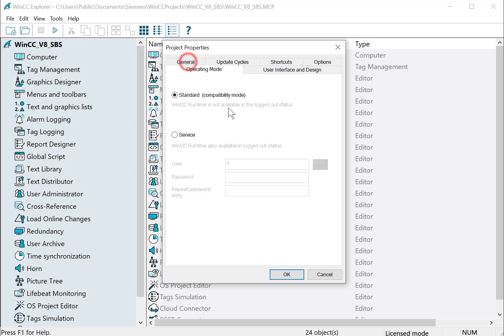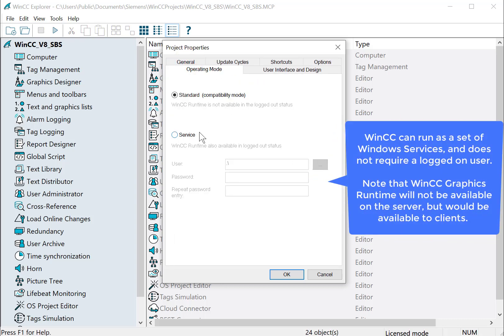And under Operating Mode, you can run WinCC as a service versus a standard. And if you run it in standard, then that means someone has to be logged on to the operating system in order to run the project. If the user logs off, then it shuts the project down.